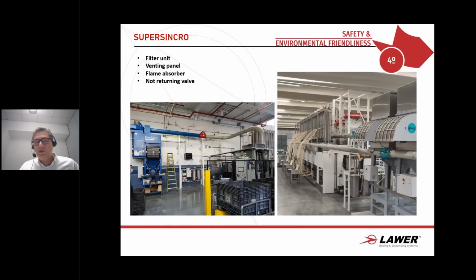The filtering unit is equipped with a venting panel. We have a flame absorber, a device that, in case an explosion happens in the filtering unit, avoids the flame escaping and contains the flame and thermal energy inside the filtering unit. There's also a non-returning valve to avoid the flame coming back to the equipment.